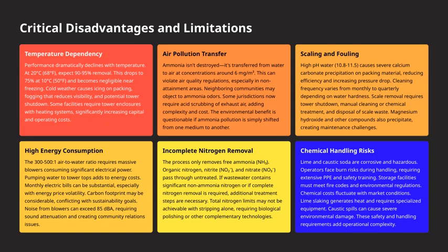Let's now look at some of the critical disadvantages and limitations of this process. First, temperature dependency is a major factor. Performance drops significantly as temperatures decrease. For example, at 20 degrees C, we can expect about 90 to 95% removal efficiency.